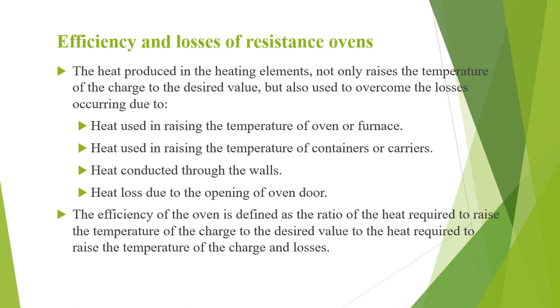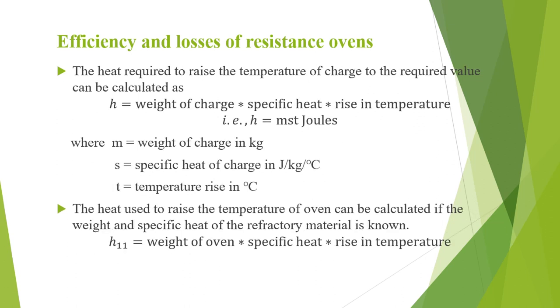The efficiency of the oven is defined as the ratio of heat required to raise the temperature of the charge to the desired value, to the heat required to raise the temperature of the charge and losses. The heat required to raise the temperature of the charge is h = m × s × t joules, where m is the weight of the charge in kg, s is the specific heat in joules per kg per degree Celsius, and t is the temperature rise in degrees Celsius. The heat used to raise the temperature of the oven, denoted H11, is given by H11 = weight of the oven × specific heat × rise in temperature.